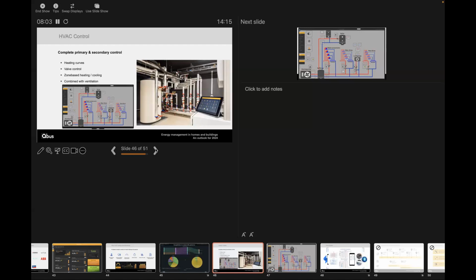Cooling here is also a pretty big part of your energy consumption. We do lots of cooling and heating installations, handling both primary and secondary control - setting up curves, valves (three-way, two-way, all kinds of valve control), zone-based heating, sensors in rooms, switches, or motion sensors measuring temperature in certain areas, and controlling heating and cooling based on that.